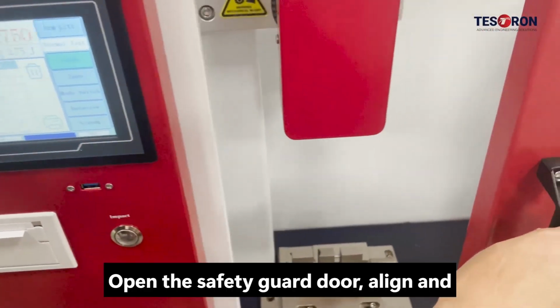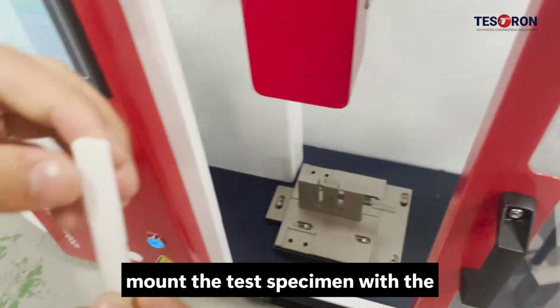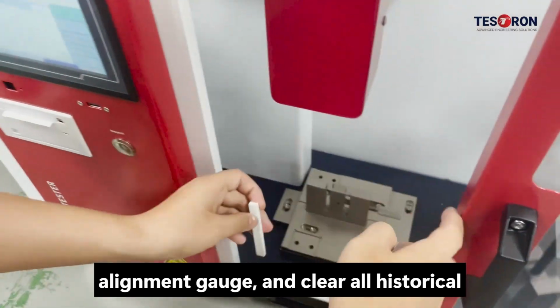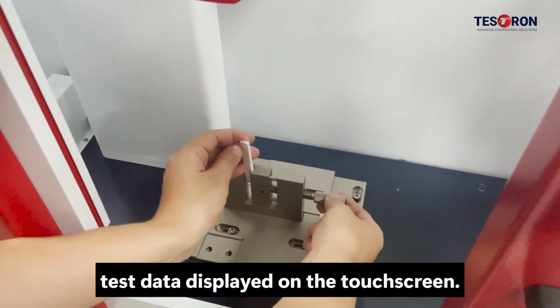Open the safety guard door, align and mount the test specimen with the alignment gauge, and clear all historical test data displayed on the touchscreen.